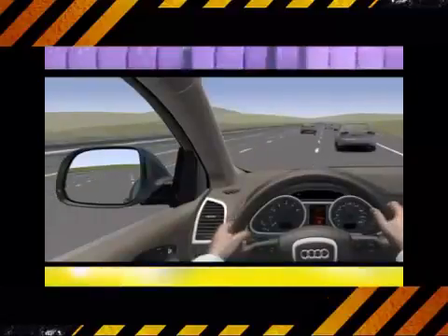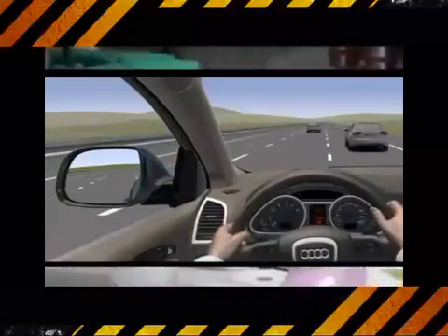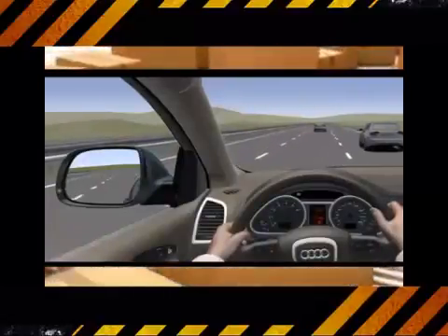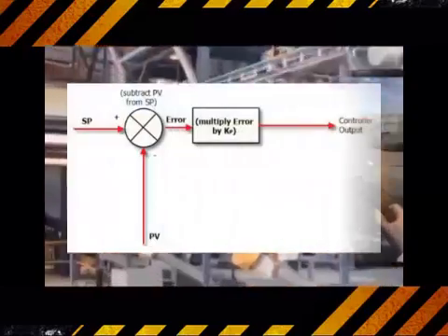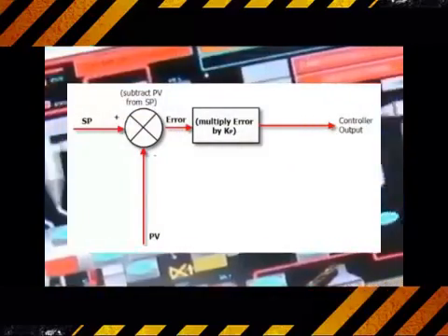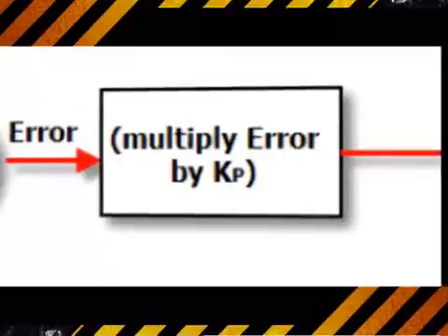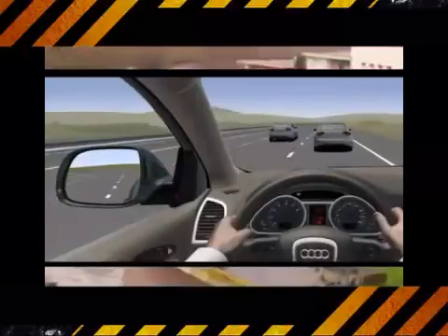The problem with this is that if you're in a hurry to get into that lane and you choose a really conservative or rather small angle initially, you will take a long time to get there. It's the same with proportional control. A small proportional gain, Kp in the diagram, is the safest way to get to set point, but your controller performance will be slow.